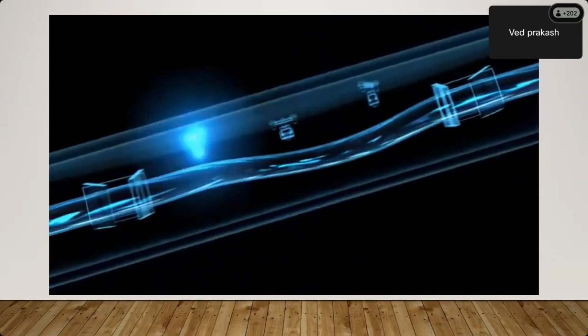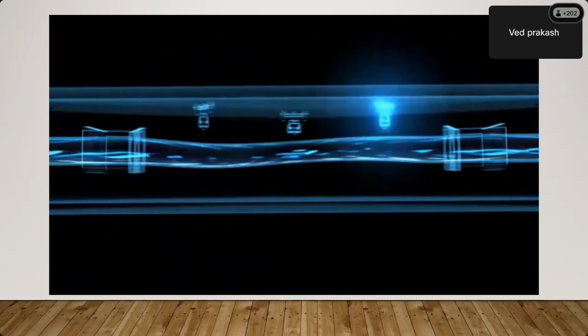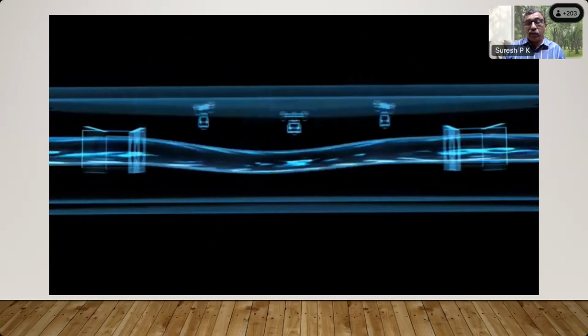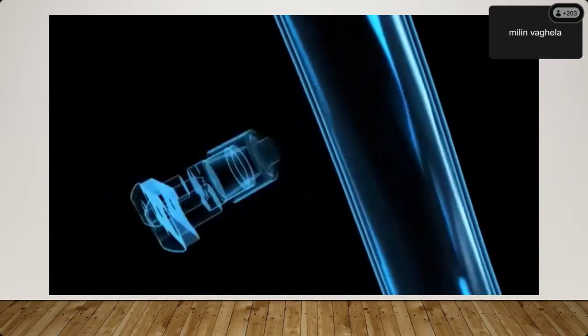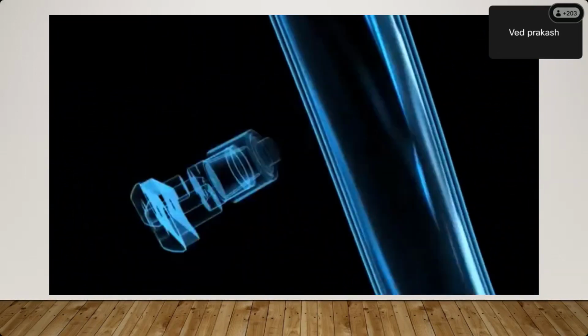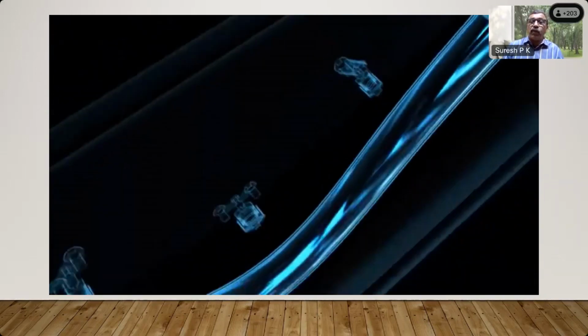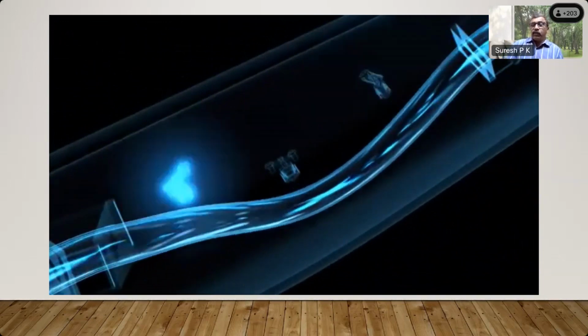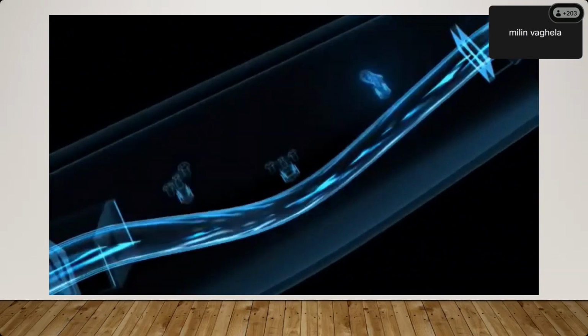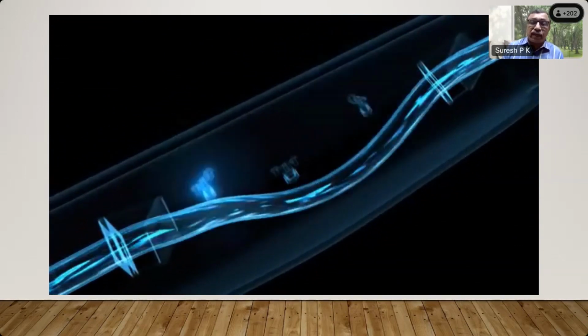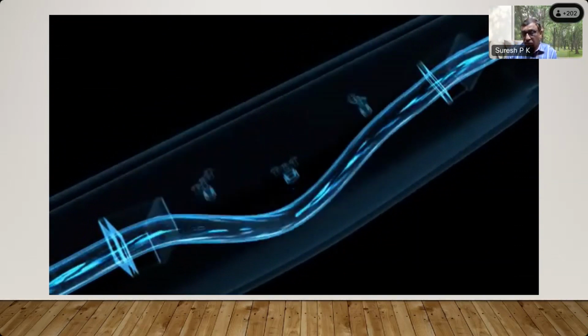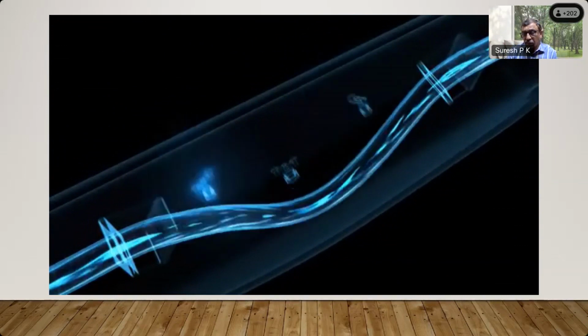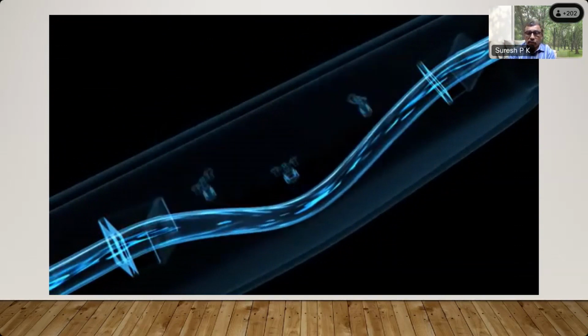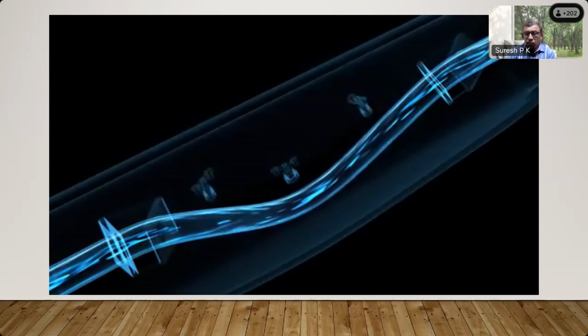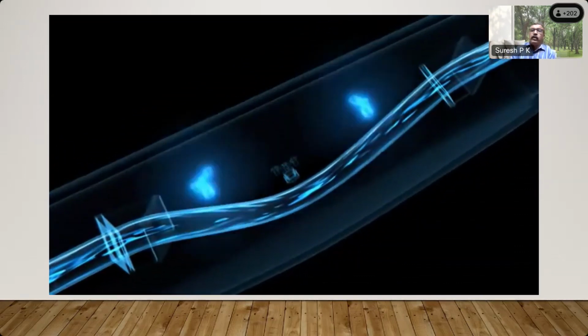See how the tube moves. This is an exaggerated view, of course. Now the flow tube experiences the Coriolis force. So the oscillation of the tube is directly proportional to the mass flow rate through the tube. These flow meters can be used for both liquids and gases, and will give you the total flow and an indication of density. Therefore, you can calculate the volume flow. The frequency gives an indication of the density of the fluid contained in the tube.